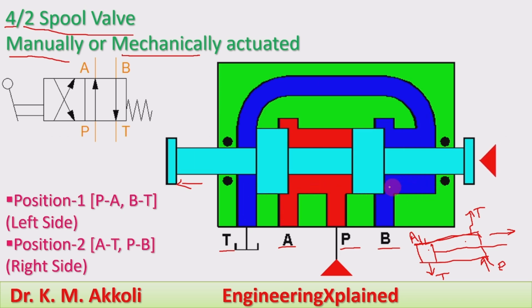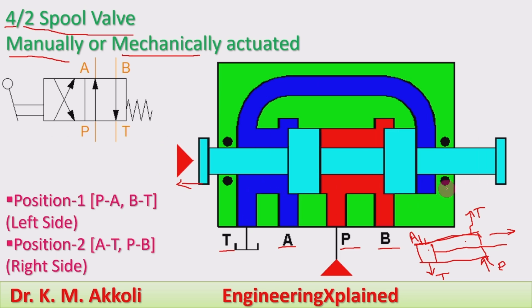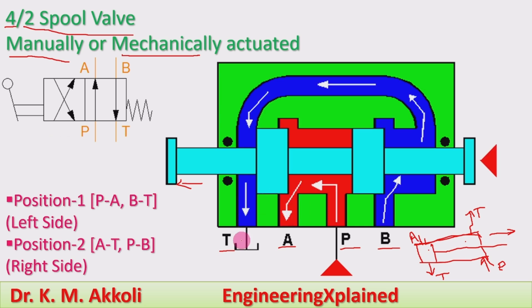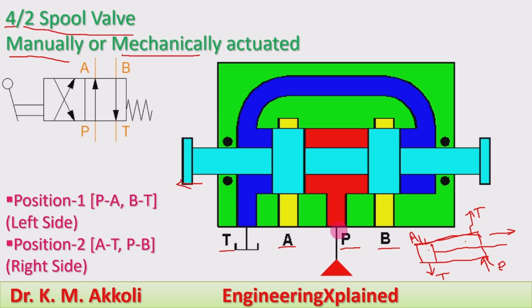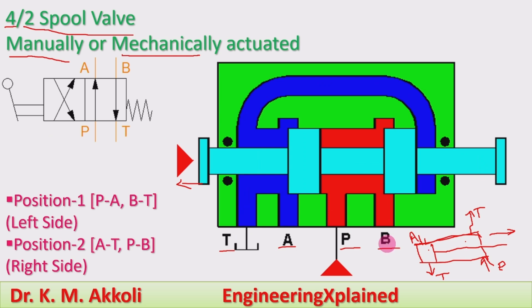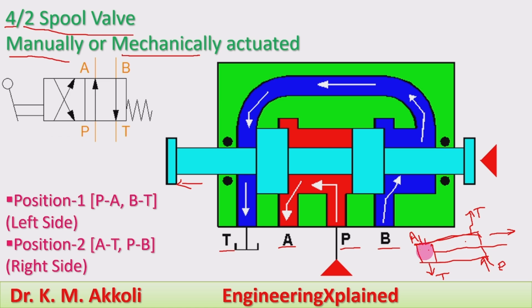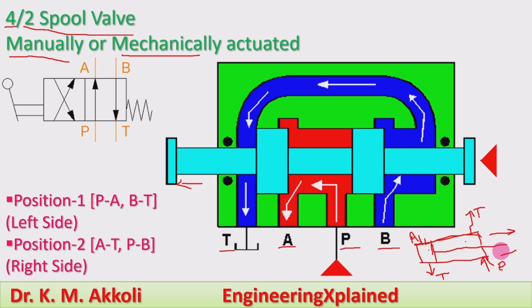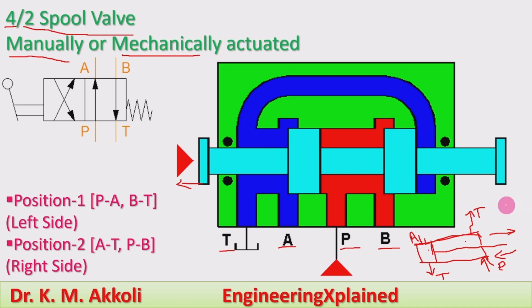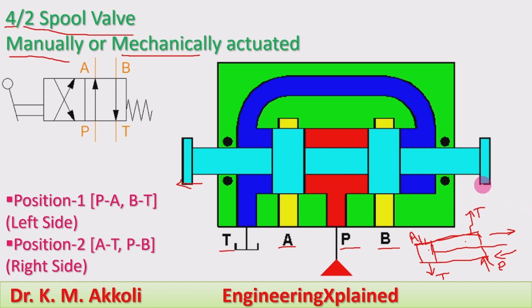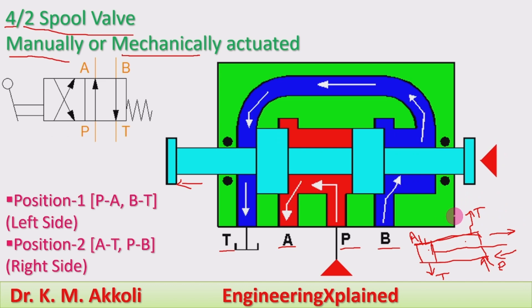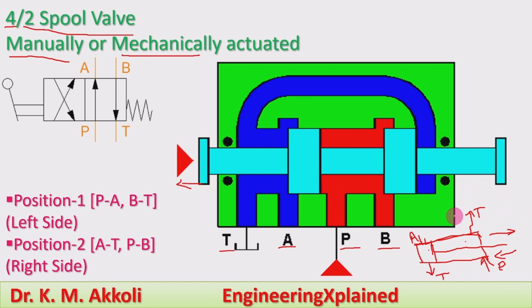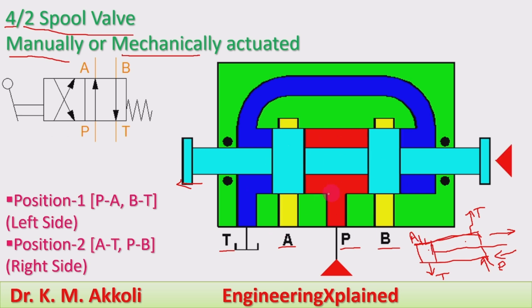Position two is the right side. When the spool is on the right side, the actuator line is connected to tank and the pump line is connected to the B port. This is the return stroke. Both strokes are power strokes here; the return will be quicker compared to the forward motion, which has more power.